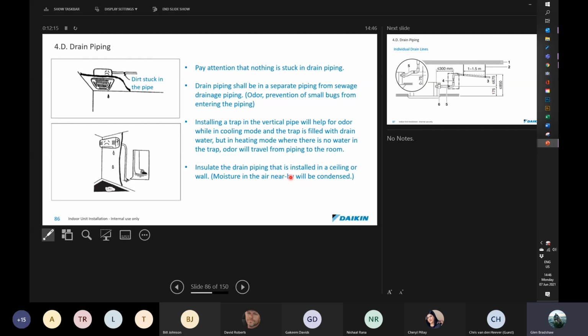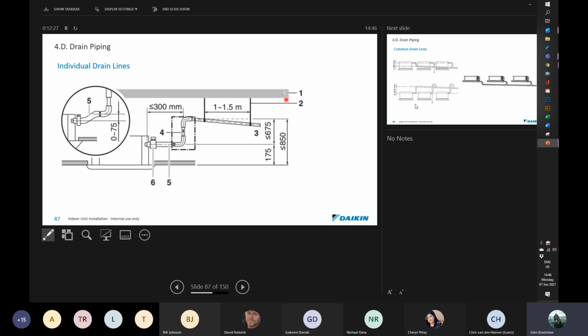Okay, and then insulate drain piping that is installed in a ceiling or wall. Okay, that's also just to stop it from sweating and dripping onto the ceiling tiles or causing a damp patch on the wall. Okay, you will also know that some of our units, our cassettes and ducted units, have drain pumps fitted in them. It's important when installing those units to remember what their maximum lift is. Okay, these do help you in installing the drain. And also make sure that you use the correct size piping. You don't want to oversize this piping because you don't want too much water flowing back into the unit every time the unit switches off. Okay, so take note of that.